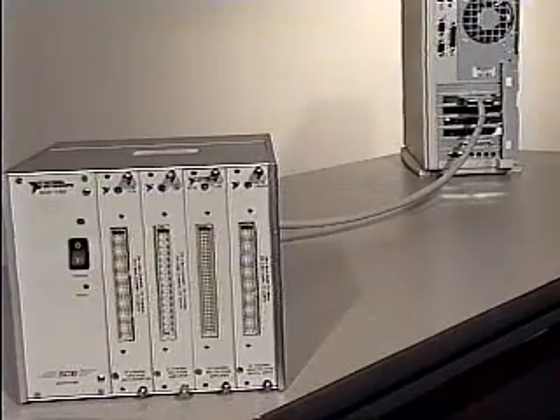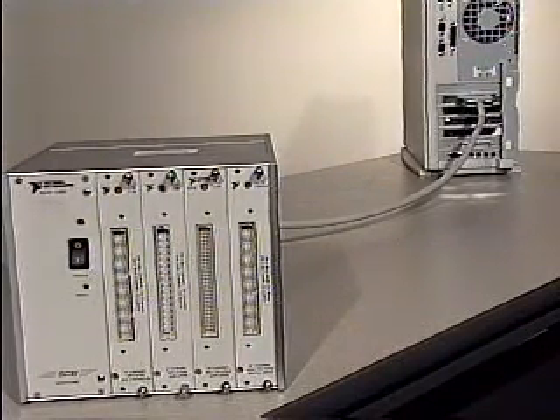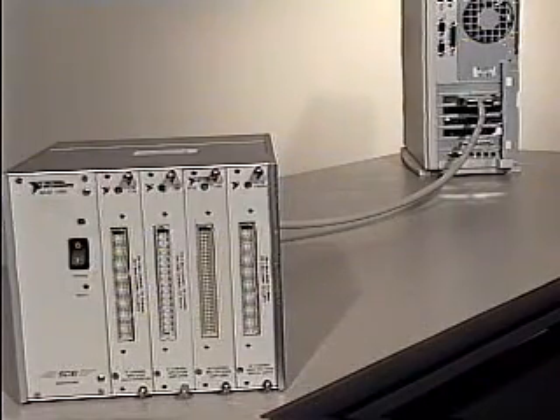The portable configuration is similar to the desktop configuration, but uses a PCMCIA DAQ card to acquire data from SCXI. As an alternate approach for a portable configuration, you can install an SCXI 1200 data acquisition and control module into your chassis and directly send your data to PC memory through the parallel port. When you need to locate the SCXI system a long distance from the PC, an SCXI 2000 chassis or SCXI 2400 module provides the RS-232 interface.